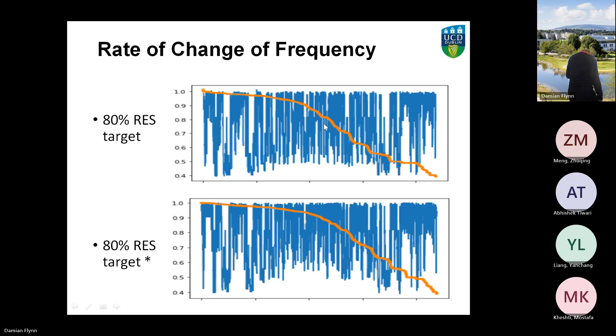So similar to GB, Ireland is looking at synchronous condensers as part of that solution, at least in the short term. The synchronous condensers provide inertia, fault level, and voltage support, and they do it at 0 megawatts, which is important.